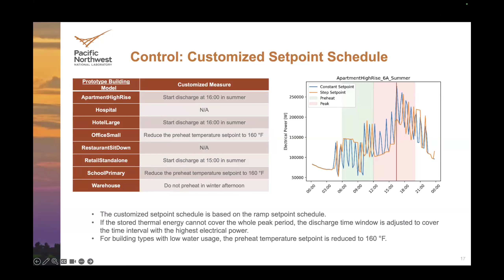Sorry about that. So that observation led us to an approach where maybe we could get better savings if we used a customized set point schedule, based on the ramp schedule, but with some changes depending on how it was interacting with the overall building load profile. For example, if the energy stored in the tank wasn't enough to make it through the entire significant peak period, which was about 9 hours for the summer peak time of use schedule, then we might adjust the point at which the aquastat set point dropped to later in that period and still see a benefit. That's what's shown here on this graphic: we're extending the 180-degree period out to the 1600 hour, and then allowing the set point to drop down to 120.